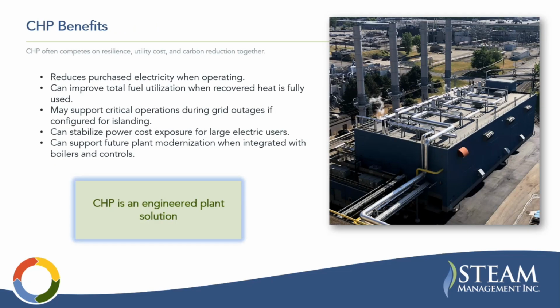Thanks, Keith. Some CHP benefits. You're going to reduce purchased electricity when operating. You can improve the total fuel utilization when recovered heat is fully used. It may support critical operation during grid outages if configured for islanding, and that's a common thing that you'll see. Facilities will invest in their own power island so that they don't have interruptions in production. It can stabilize power cost exposure for large electrical users and can support future plant modernization when integrated with boilers and controls.